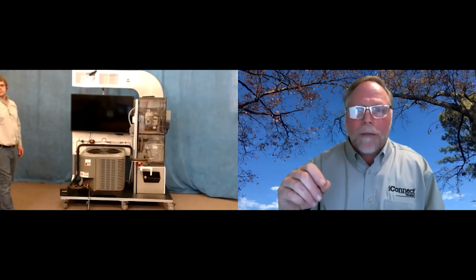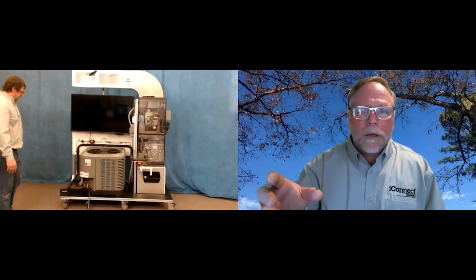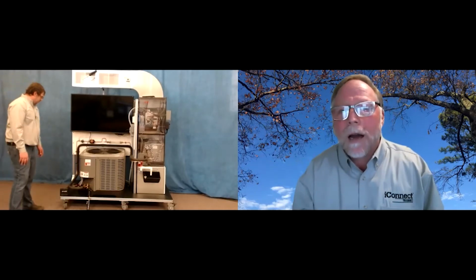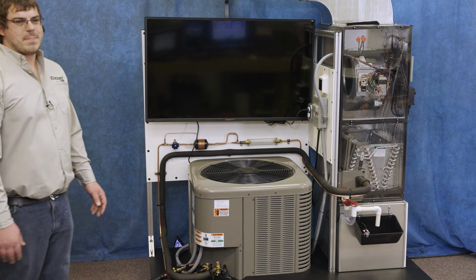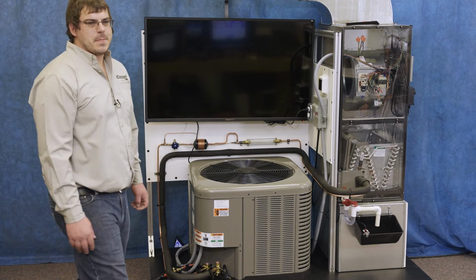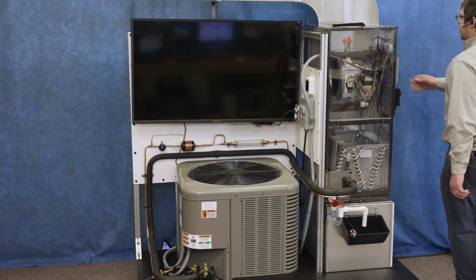Now, you know, for lesson number 1, where we lost the condenser fan motor, I wanted to see what happened to the head pressure. But right now, you look, and we've got about 148 suction and about a 225 head, and it's still going to go up some more. All right, well, Nick, go ahead and go to the troubleshooting box and turn the outdoor fan off, and let's watch those pressures.